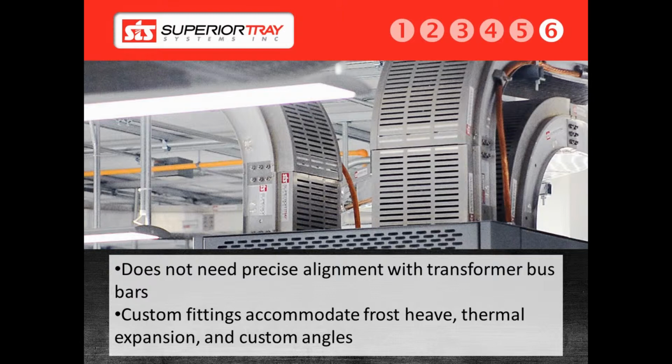On large projects, we generally suggest that the customer buy a few extra straight sections of a length of their preference and hold it on site in case they have a problem and the system has to be modified. If the switchgear is 4 feet further than expected, they can cut the extra 4 feet from the extra straight section and install it. This saves the customer costly downtime while they wait for us to manufacture and ship them a custom section.